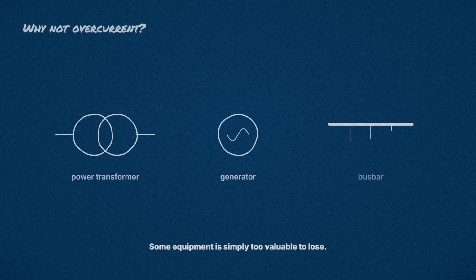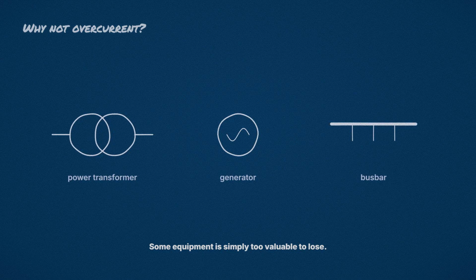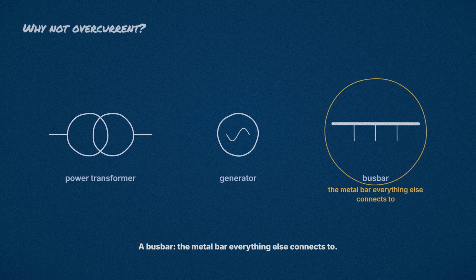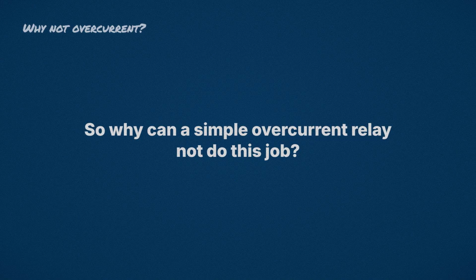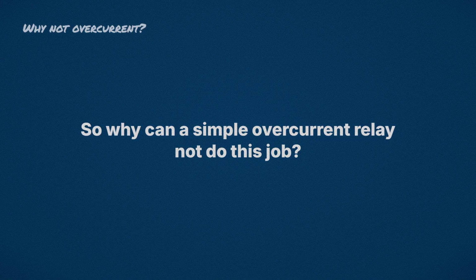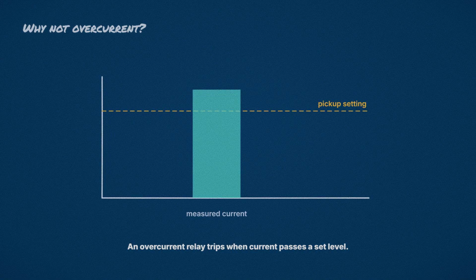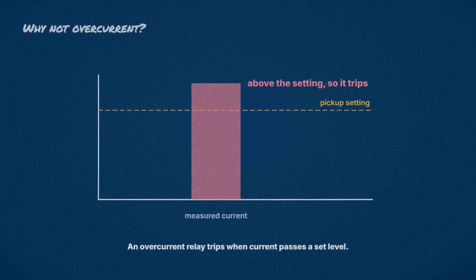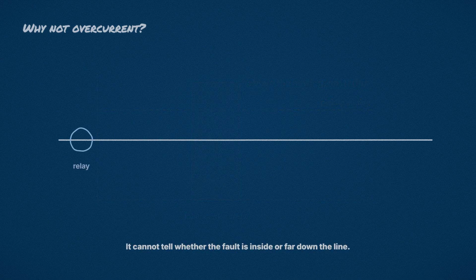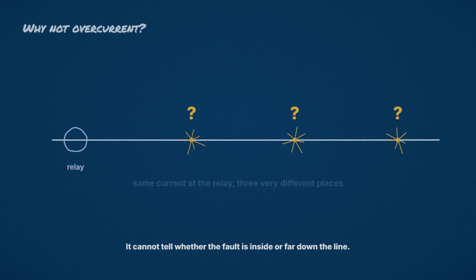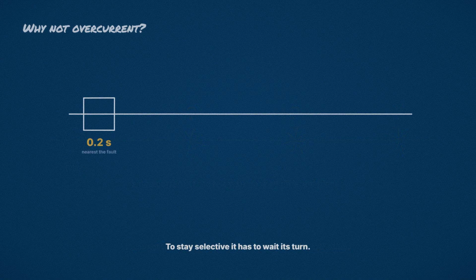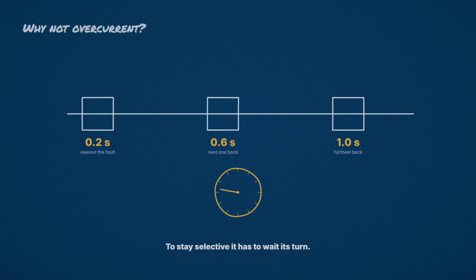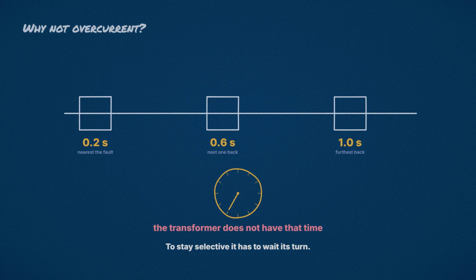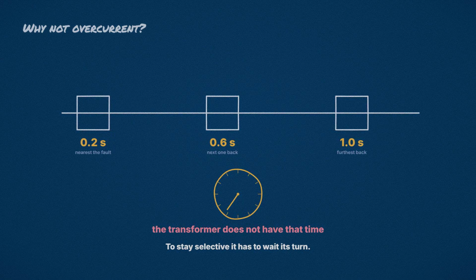Some equipment is simply too valuable to lose. A large power transformer, a generator, or a substation bus bar, which is the metal bar that everything else in the substation connects to. So why can a simple overcurrent relay not do this job well? An overcurrent relay is a relay that trips when the current rises above a set level. That is all it knows. It reacts to any large current, and it cannot tell whether the fault is inside the transformer or far down the line. To stay selective, it has to wait and let the devices closer to the fault act first. That waiting is time the transformer does not have.